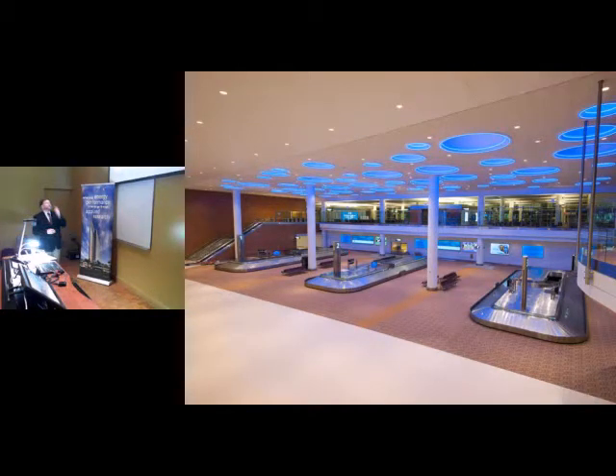So one of the design concepts we explored was, was there a way to ventilate, heat and cool the space without having to ventilate and heat and cool the entire volume of the space. We ended up working with what's called the displacement ventilation system. What it does is it brings high volumes of air at low velocity into the space, at lower temperature as well, and that causes the air to stay close to the ground. It doesn't tend to rise as heated air typically would do. So we're not shooting air down anywhere from the ceiling trying to heat or cool out the floor.